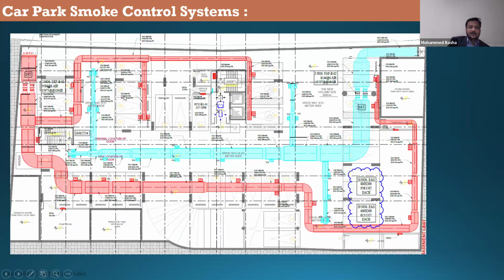So this is an example layout. As you can see, the red color is the exhaust. If you measure, no place in the car park exceeds 12 meters. And this is the fresh air supply system complying with QCDD standards. In this example you can consider a velocity of 8 or 9 meters per second. Do not worry about the velocity here, because it is going to operate only in fire mode, so the sound requirement is not going to be a concern.